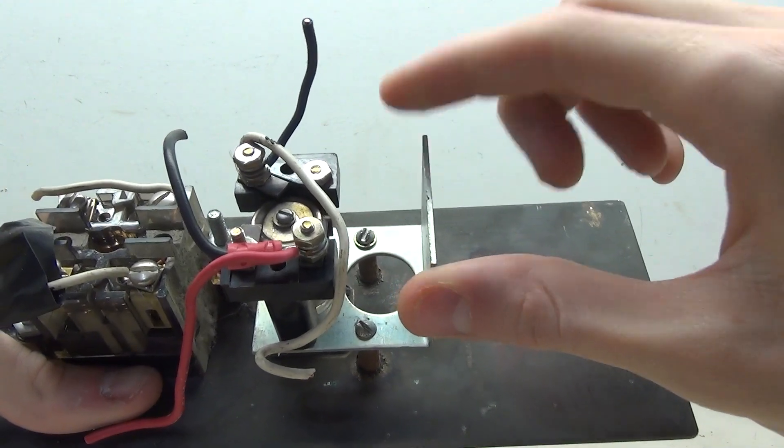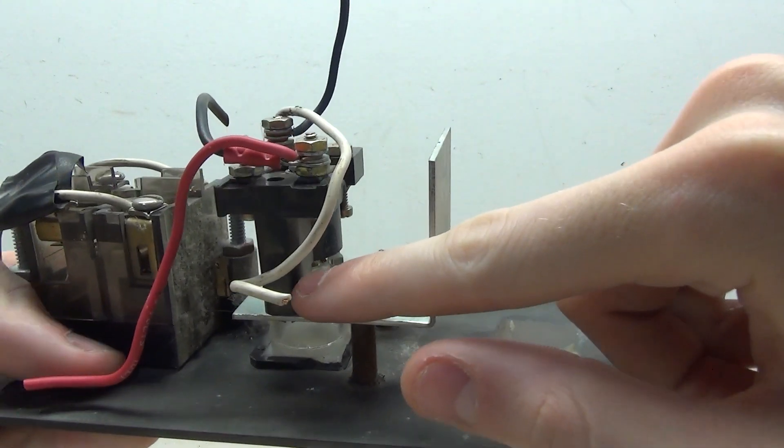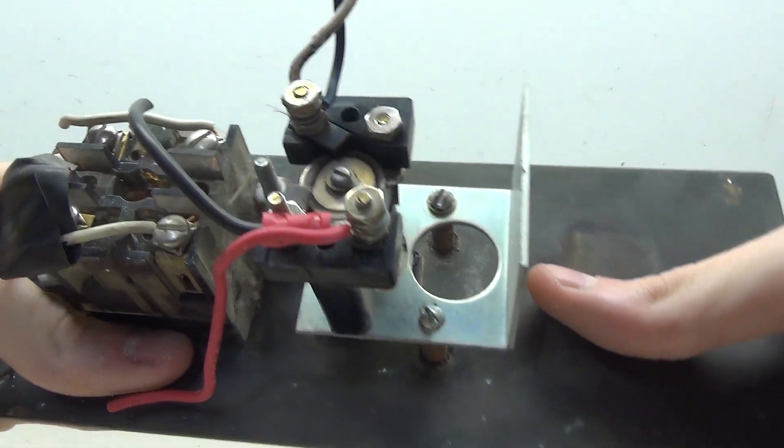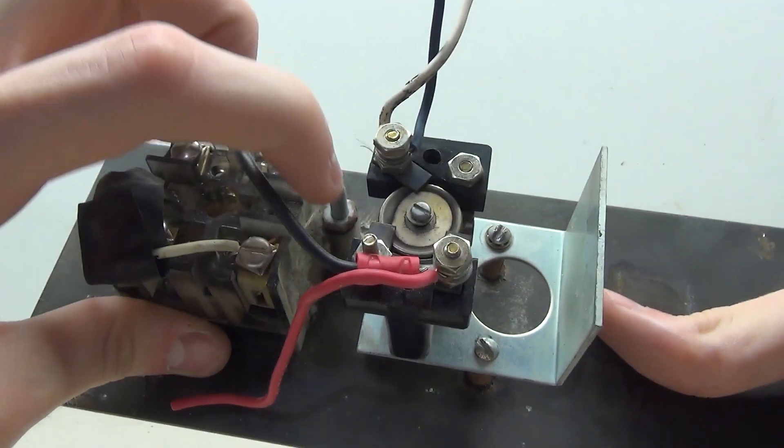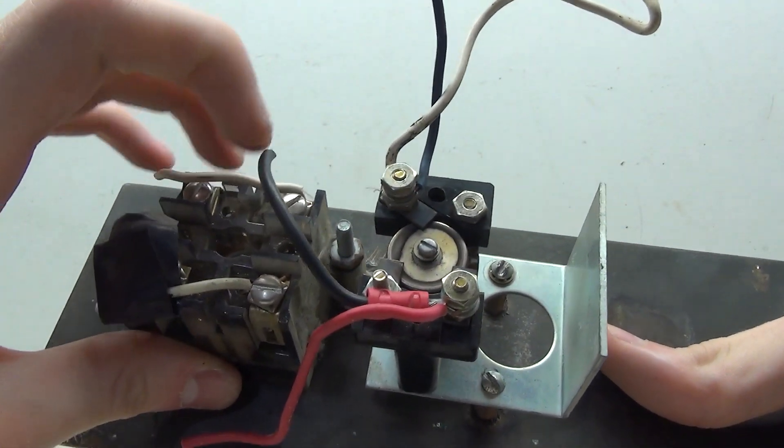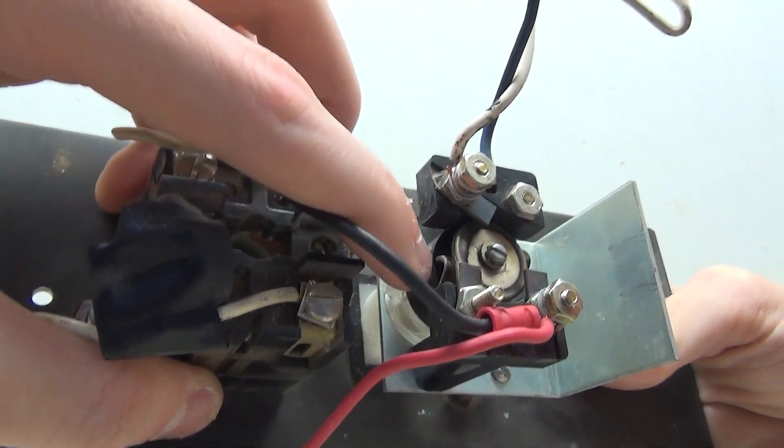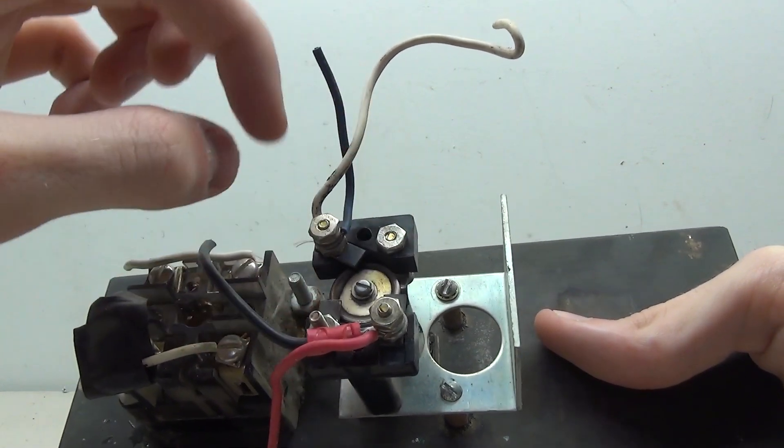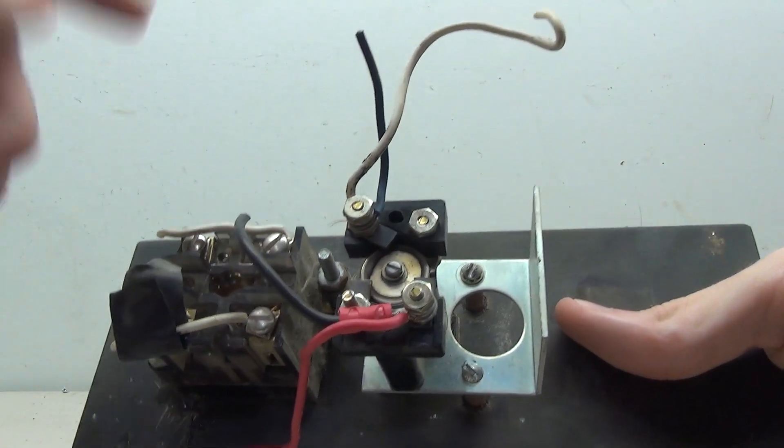Remaining here there is this metal bracket which is what you clip the lamp holder on. Then there is the contact here, and this is the same kind of contact that's used on older Montgomery buttons. It's got this disc and when you press the button in it pushes the disc against these metal contacts completing the circuit. This particular button does feature the normally closed contact as shown by these two here. So these two pins here would serve as the normally closed contact, and then you could pretty much use any of these three here as the normally open.